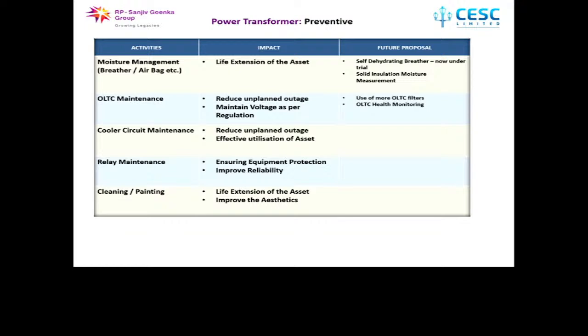Cooler circuit maintenance: some of the old transformers, 20 MVA or 16 MVA, which are 33 by 11 by 6 kV, used to have cooling fans in them. All the 132 kV or 220 kV transformers have cooling fans, and also a few transformers we have with cooler banks. So the cooling fans and these cooler banks require some regular maintenance.